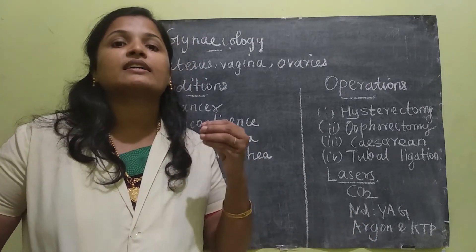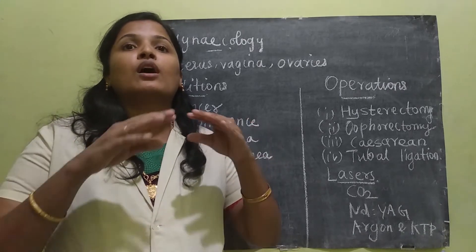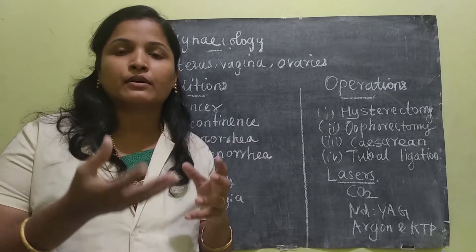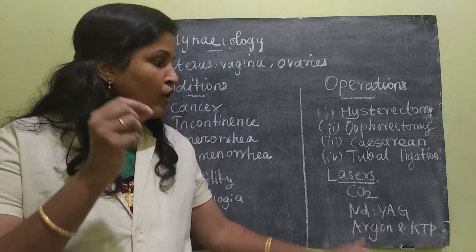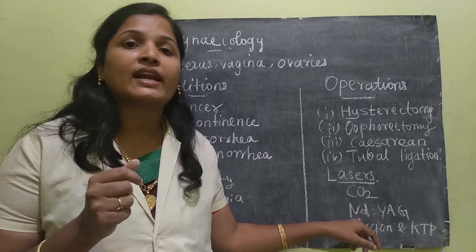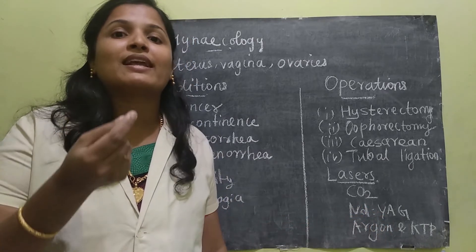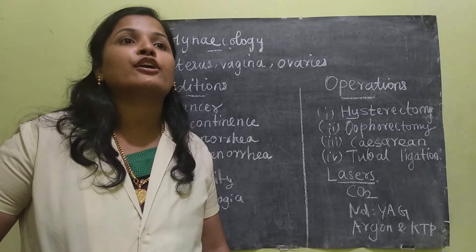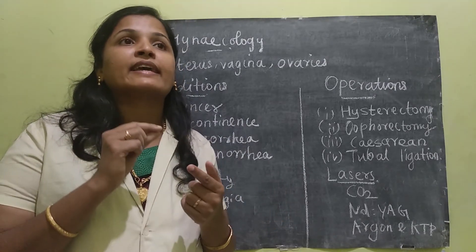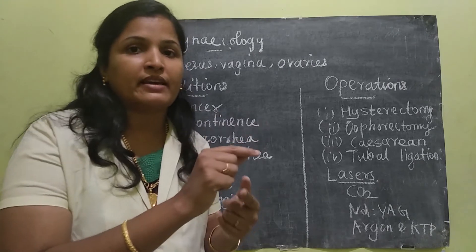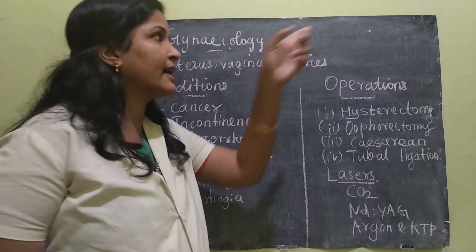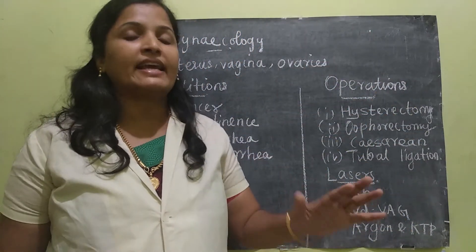Nd:YAG lasers act as deep coagulators. Coagulation means clotting the blood in order to have removal of tumors. The Nd:YAG laser also uses a helium-neon laser for aiming. Helium-neon laser is a low-power laser used as a pointer to target the surgical part.